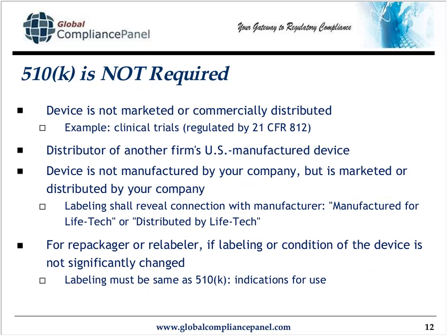You're not the manufacturer. If the device is not manufactured by your company, but is marketed or distributed by your company, in this case, the labeling has to reveal the connection with the manufacturer. If a company named LifeTech, for example, is the distributor, they may choose to indicate on their labeling manufactured for LifeTech or distributed by LifeTech, whichever one. Either of these clearly indicates the connection.